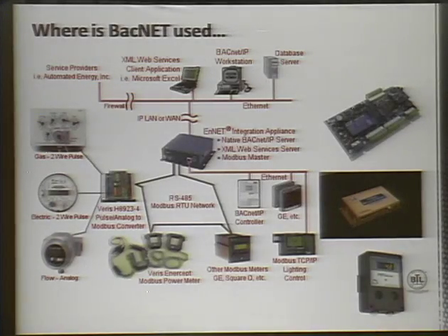So here's a high level of what a BACnet network kind of looks like. And the stuff you see at the very top are the things that we're used to seeing. These are the building management systems, the SCADA systems. These are the systems that our admins or facility workers are used to putting their hands on to read and control. That device that you see in the middle, the blue, goes by a lot of different names depending on which vendor you talk to, but basically it's called a BBMD device, BACnet Broadcast Management Device. Some vendors call it a router, some will call it a gateway, and some call it a couple other things.